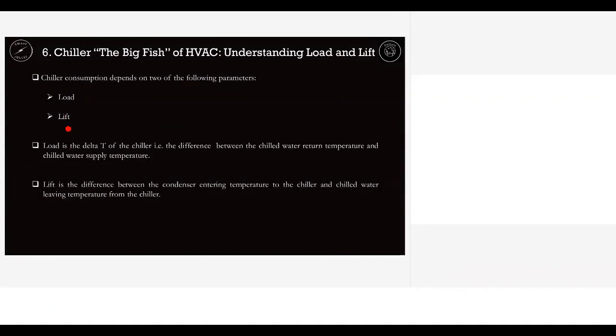To identify it through data, delta T is the difference between the return and supply temperatures of chilled water, that is load. And lift is the difference between the condenser entering temperature, that is the outlet temperature of the water coming from the cooling tower, and the cold temperature, or the chilled water temperature leaving the chiller or the evaporator to the building. The difference between these two is called the lift. So keep these two things in mind. They are universal. If you want to save energy from centralized air conditioning, or from any of these associated processes, you need to be very thorough about these two terms.